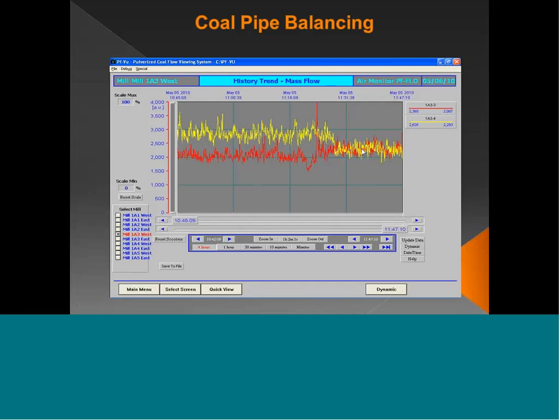I want to stress again that each measurement is individual and independent. We don't compare signals. There's no relative relationship between the two. We're measuring the mass and the speed in each pipe, and all we're doing is comparing it. So the yellow pipe's mass is decreased, and the mass shows up in the red pipe, so we know we did our job. If I were to show you the velocity screen, which I didn't include in this presentation, the velocity in the yellow pipe is also going to decrease, and in the red, probably increase.